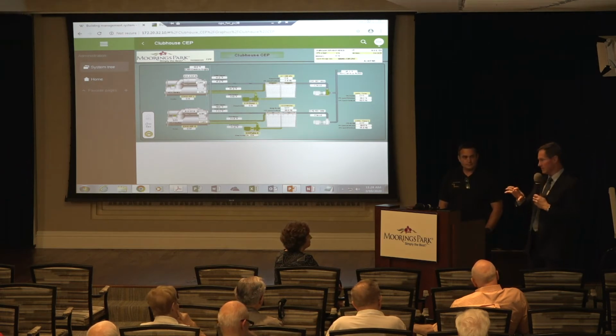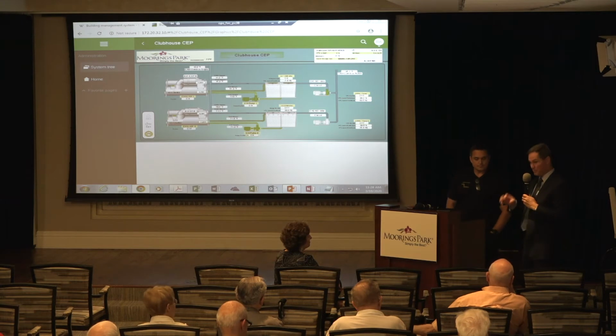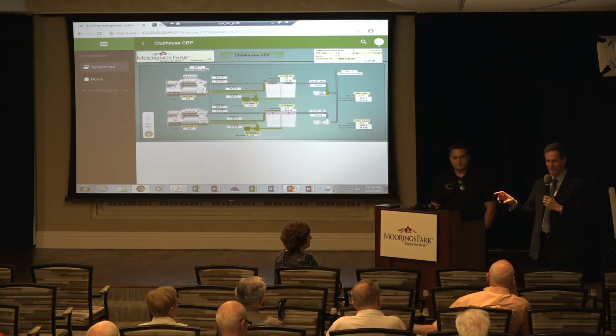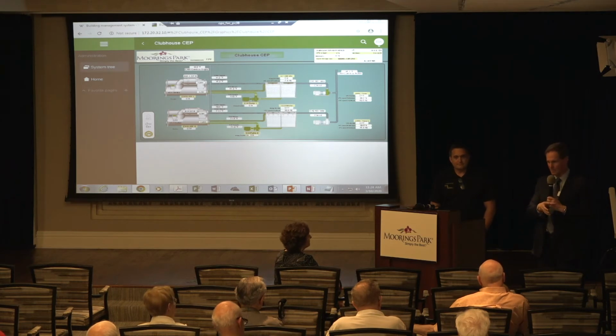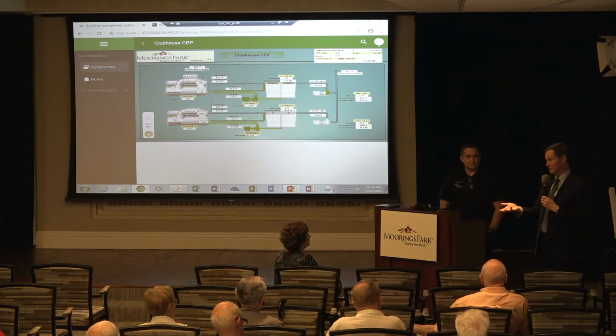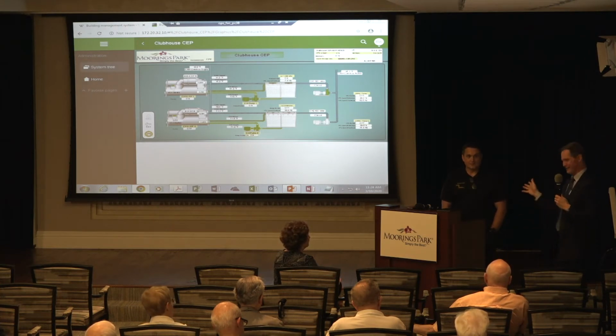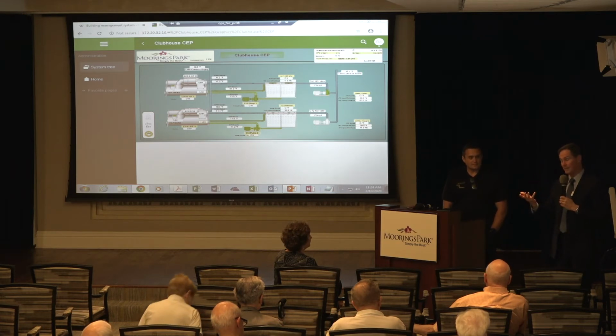I've also seen systems, and Mike can probably attest, where people get in there and start moving things, and the building doesn't behave like it was designed to. Especially if you start messing with the amount of outdoor air you're bringing in, especially in this environment, you can bring in too much humidity and can't remove the water from the air. Our buildings will have issues. That's where you've got to limit your controls and access, because you can really get things off kilter.